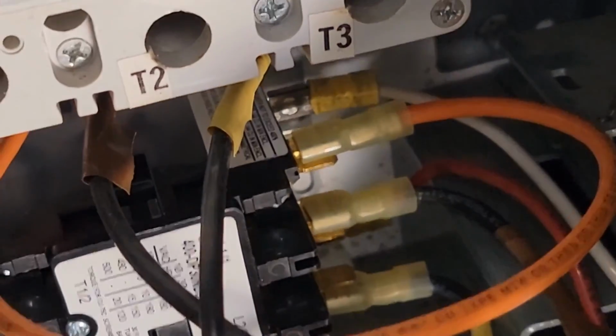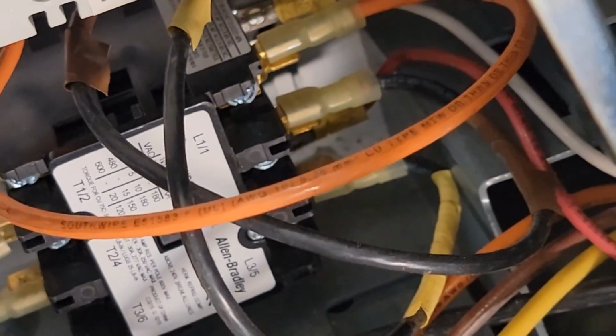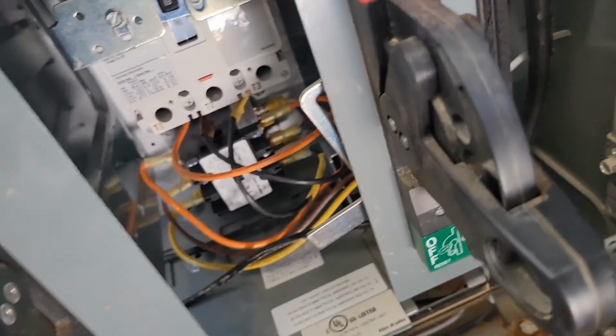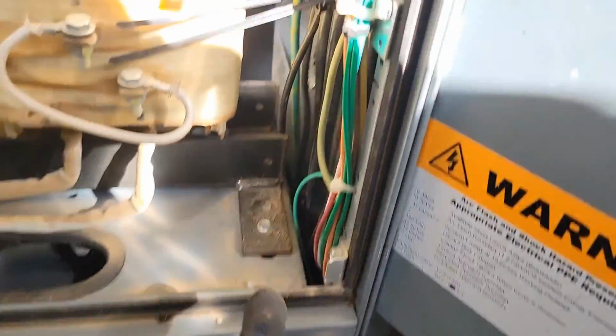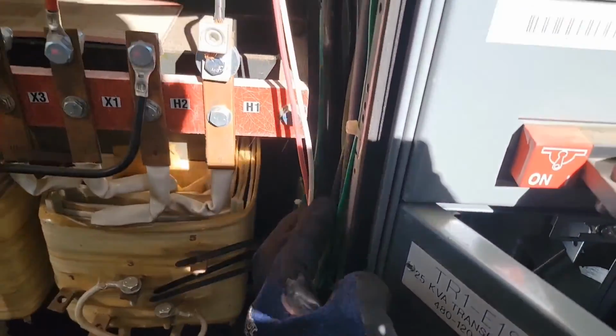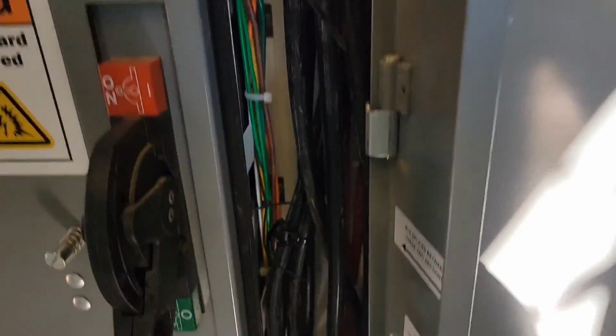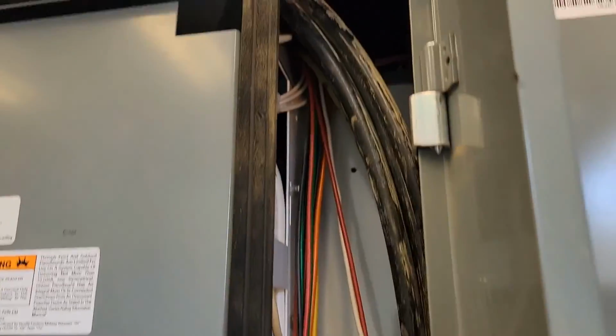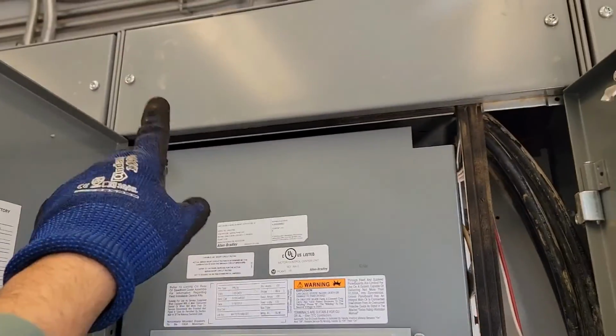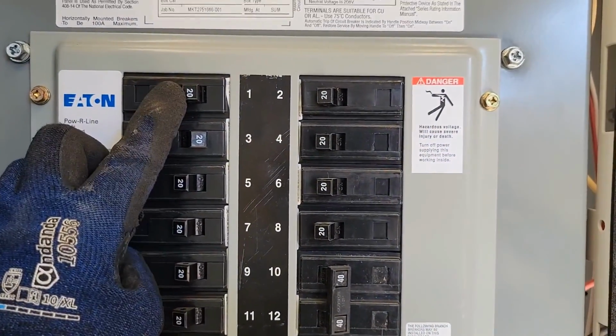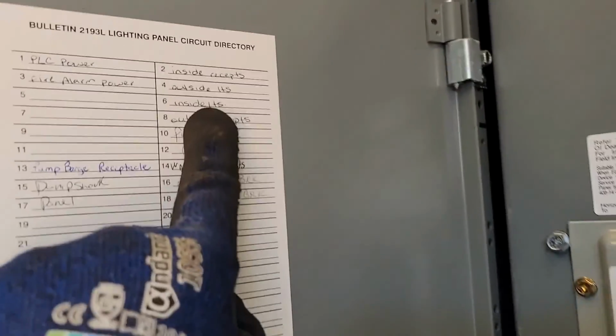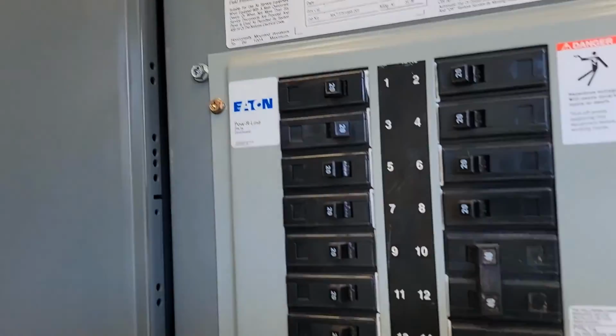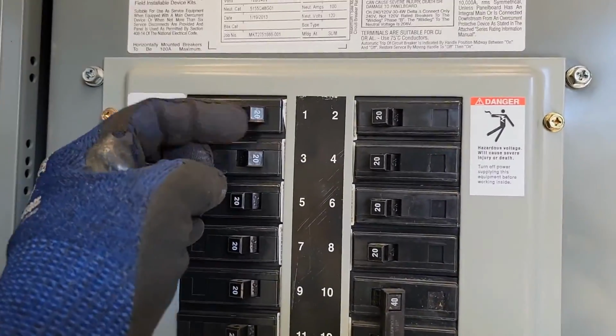So let's find out. Okay, so there's a white wire and a red wire, and you can barely see it, but I checked the voltage to the coil, and of course we don't have 120 volts, and I traced those wires, and they go down here, then they go through here, and then they go up in here all the way up right here. And before I could take this panel off, I noticed something. Trip breaker. And it says for PLC power. Yeah, that's number 1. So I'm just curious.